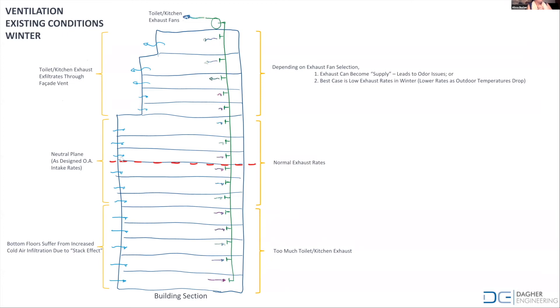Another aspect of the project: we know that building ventilation is essential to controlling energy costs. The original building system had really unregulated air intakes in all of the living spaces associated with the air conditioning units. On the lower floors, there's a serious stack effect in the building, so the lower floors had a huge amount of air coming in. The pressure build-up at the top of the building was actually made up by air coming out of the bathroom vents — not a desirable situation.